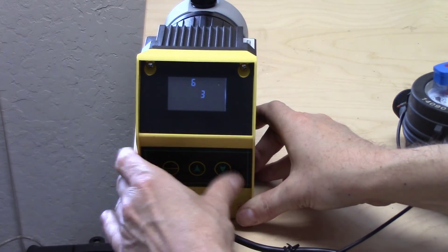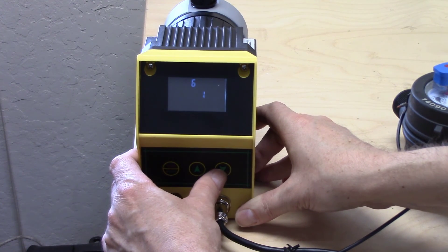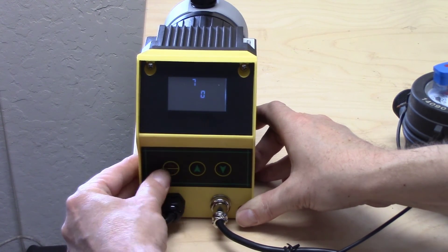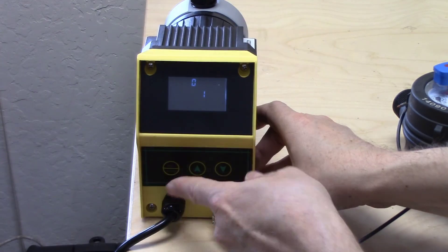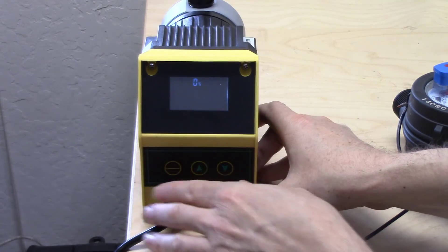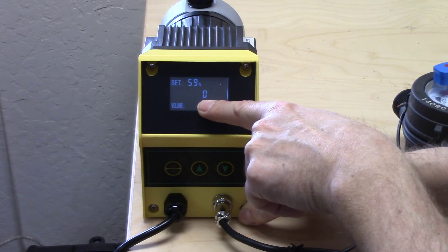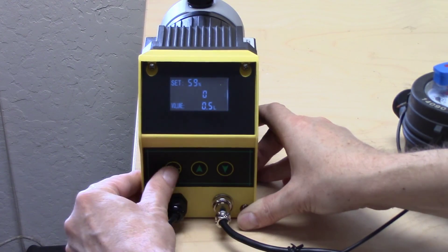Six is how many pulses per gallon. Three pumps, three squirts per each gallon, one squirt per each gallon, whatever you have set it at. Number seven is nothing. Number eight is nothing. You're back to the beginning, and then either wait or long press, hold it, it goes back. You're back in manual. Poke it again, and now once again I'm back in non-manual because I set it on pulse, and that's how it works folks. Thanks.